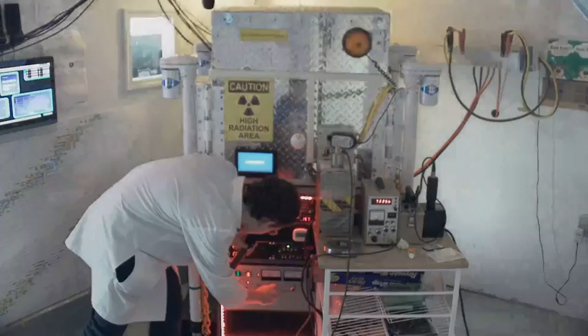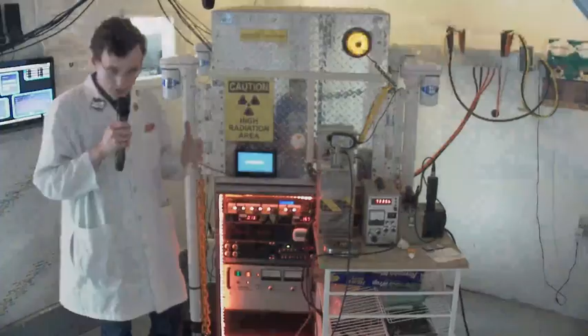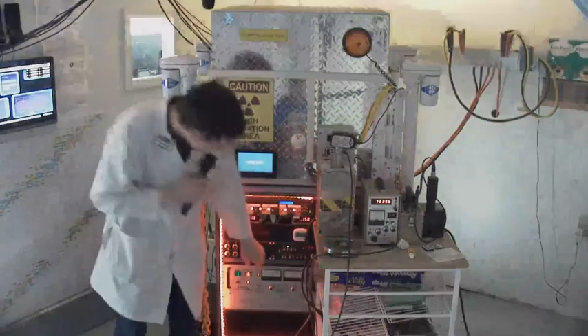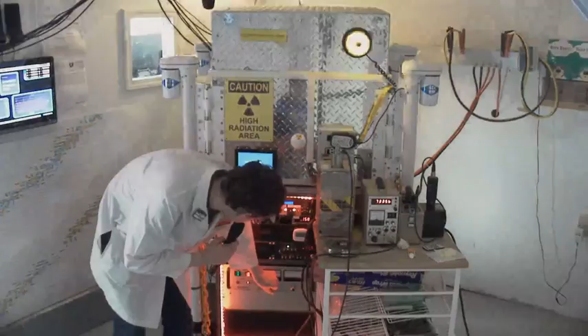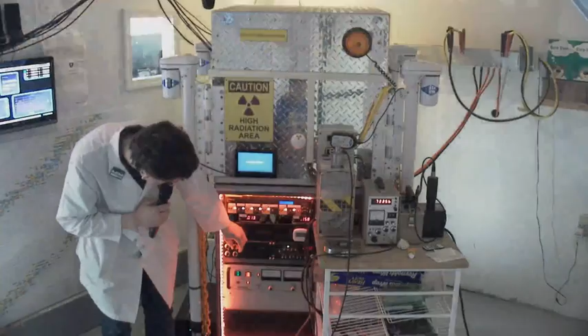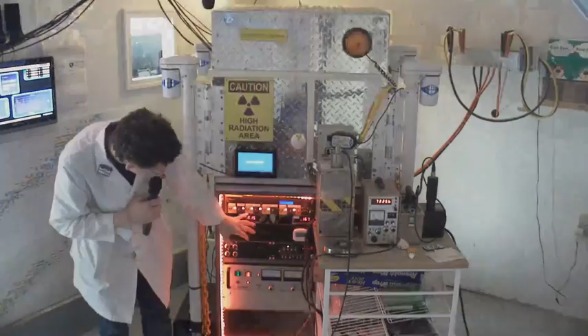We'll just drop the current down, just to get stable. There we go. So let's think about this. The vacuum pumps on the scene are running at the same speed all the time. I haven't touched the vacuum pumps at all. So if I change how much gas is going into the chamber, I'm also going to change what pressure I'm seeing right here. I'm just going to drop this current down a little bit more. So if I increase my gas flow, you'll see that... Oh, I decreased it there. If I increase my gas flow, you'll see that my pressure starts to climb.